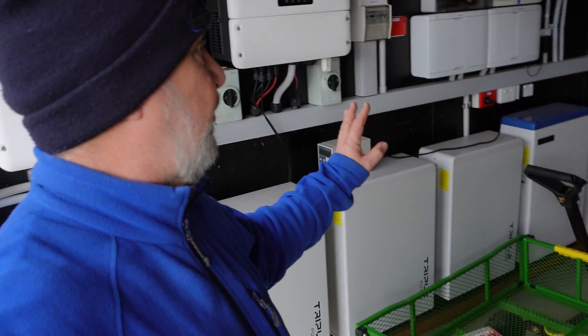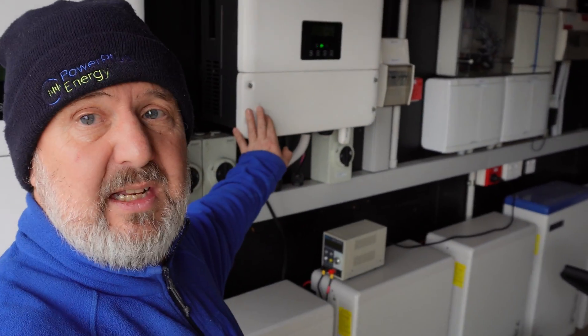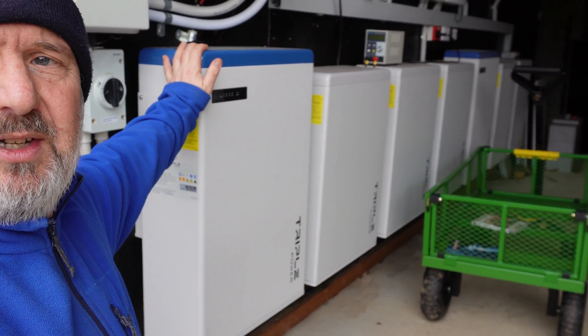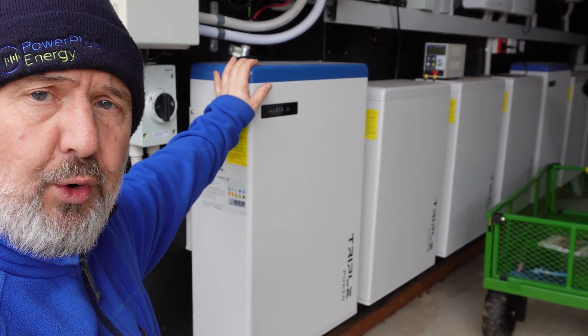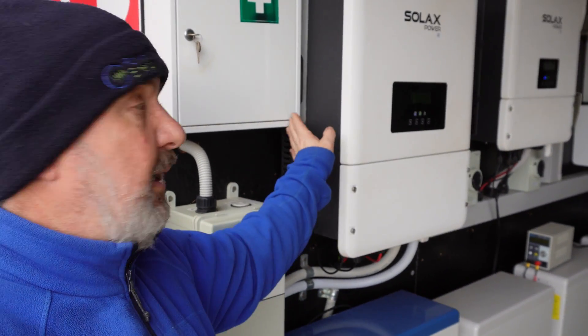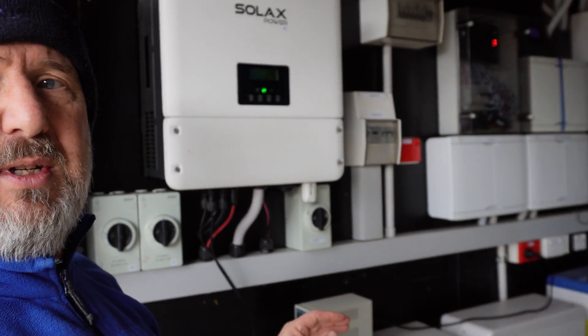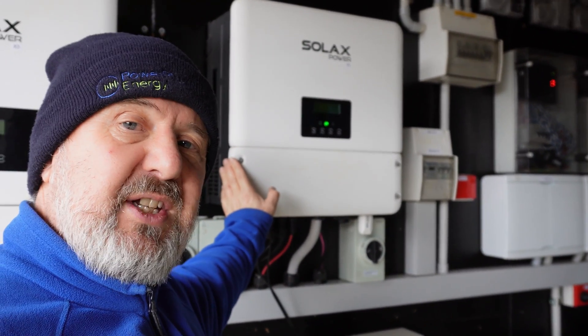On this side of the room we've also got some SolaX. We've got the three-phase SolaX inverter here, and next to it the single-phase SolaX inverter, with really lovely Triple Power batteries. There are seven of them — 100 volts each, connected in series. The first four, giving 400 volts, are connected to the three-phase SolaX X3 inverter. The next three are connected in series to give 300 volts, connected to the X1, which is a single-phase inverter rated at 6 kilowatts.